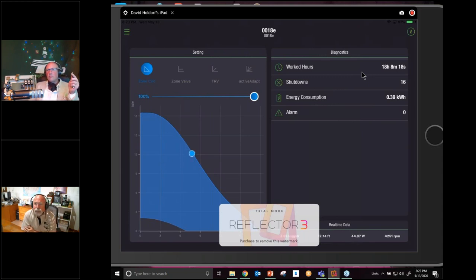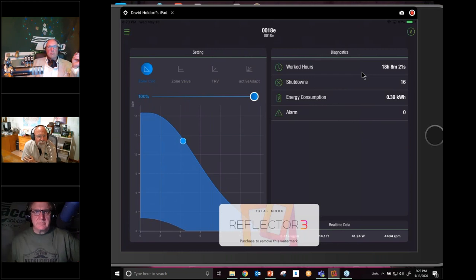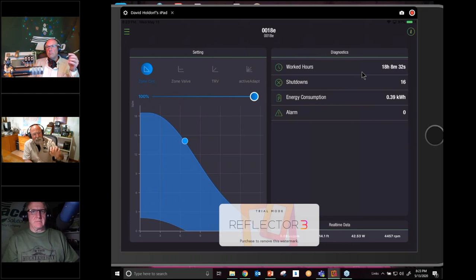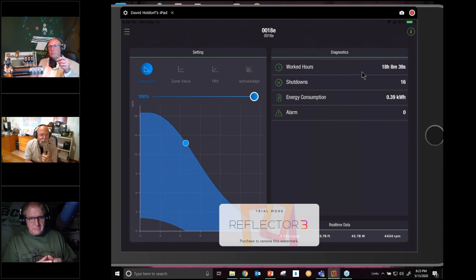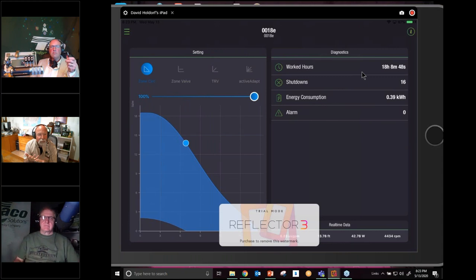Hey, Dave, will you be my hands? I want to give them another scenario and some things I've taught on this as well. Sure. Under the fixed speed application, with it maxed all the way out, it takes maybe 10, 15 seconds to find its happy spot. That would be hydraulic equilibrium, sitting right there nice and steady. Now, this is for those jobs. Let's set the scenario. It's midnight, New Year's Eve. You're not going to do any calculations. You have no idea what the GPM requirement is, but you're pulling out one old fixed speed pump and putting in this new pump, and it's a zone valve application.